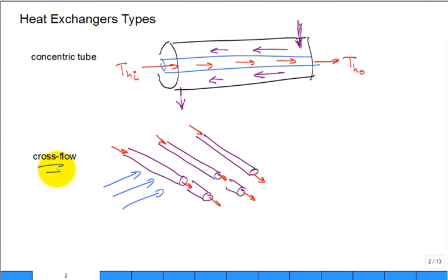Almost all the time, the tube has some surface conditioning on the inside as well as on the outside to help promote heat transfer in real heat exchangers. The other thing that can happen is they could introduce a finned material. Maybe you have circular fins around each of the tubes to help promote heat transfer, or you could have a plate that connects a lot of them together. And there's different configurations for that. All right, so one surface can or is often finned. It's the air side that's finned, not the water side or the refrigerant side or the liquid side.